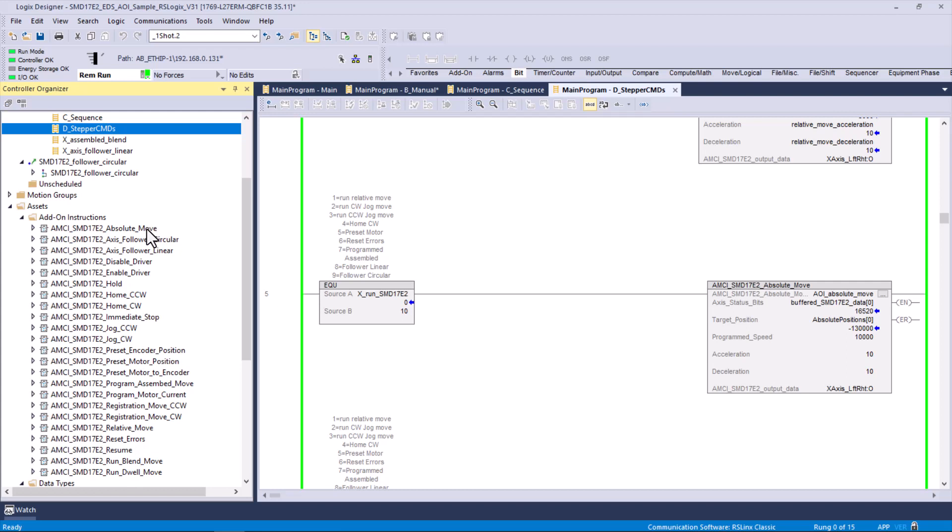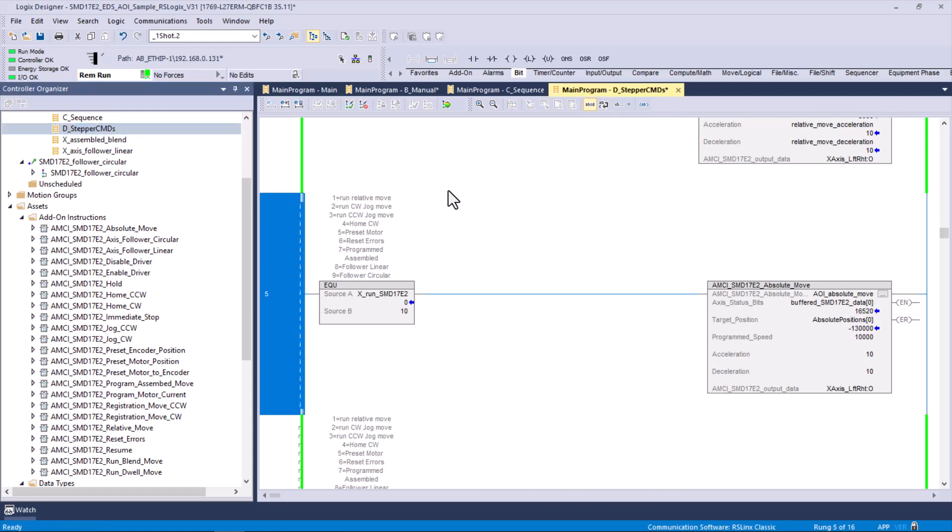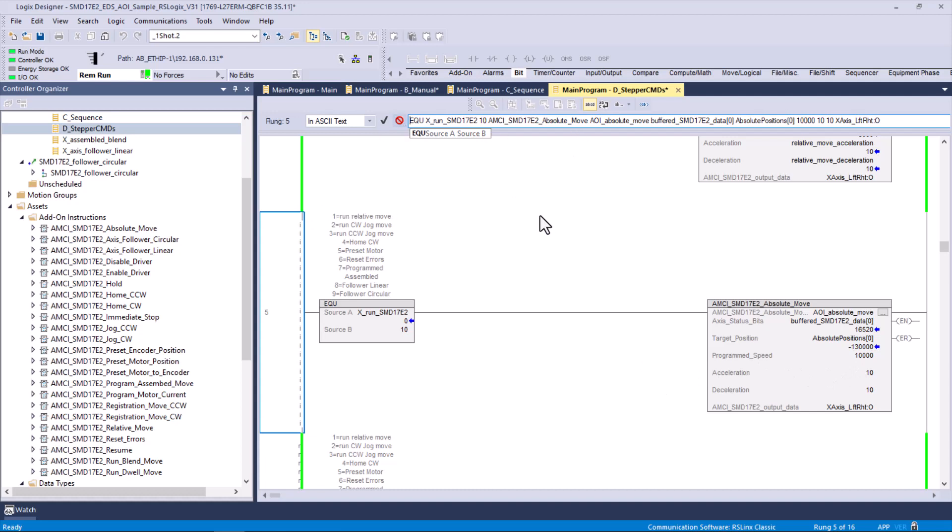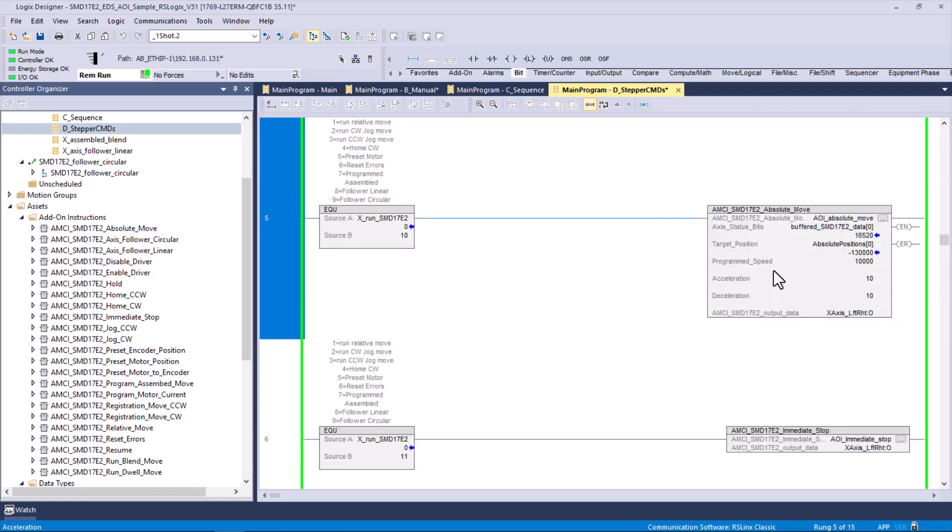In alphabetical order, absolute move. That is not in your sample program. I just went in, I put in, if it's equal to 10, I added an instruction by typing this in: AMCI SMD17E2 absolute underscore move. In other words, I added that. I typed that in, hit enter, and the instruction popped up. I did not create this instruction. I added it, though. Then you have to fill out the information you need, and you ought to be able to figure that out from the instructions you have, like this one.